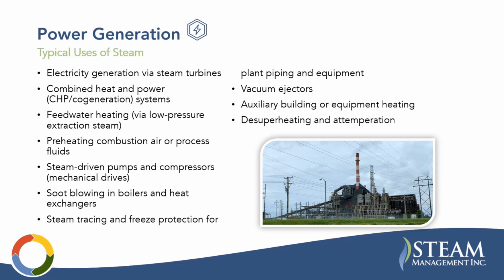Feed water heating is more steam use in the boiler house, but also preheating combustion air for the boilers, steam-driven pumps and compressors, soot blowing in boilers and heat exchangers. That's more for coal and biomass boilers, where you're basically blowing off the coils using steam to clean them and maintain your heat transfer efficiency.